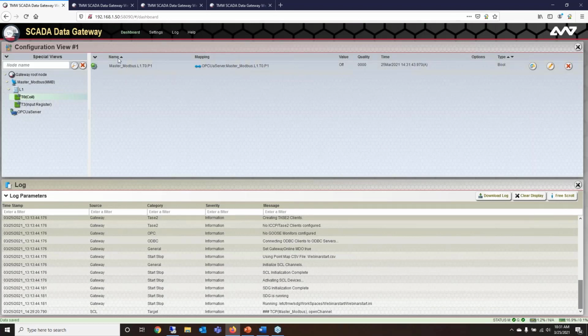So what we'll see is we've got a name here. It's the master Modbus. That's the device it's in. We've got L1, and then we've got T0, which is the coil, and P1, that's the index. And you also see that that value is off. Now, if I go over to DTM and I change that value, you actually won't see it update here automatically. And that's because we haven't told it how to transfer data yet.